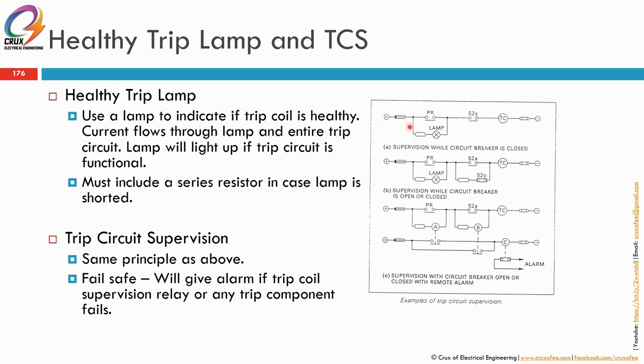Alright, so under normal condition, there's a small current flowing through here, through this contact 52A to the trip coil. So if this circuit is true, meaning there's no disconnection, no broken wire or anything, this lamp will light up, indicating that your trip circuit is healthy. So it includes a series resistor in case the lamp is shorted.